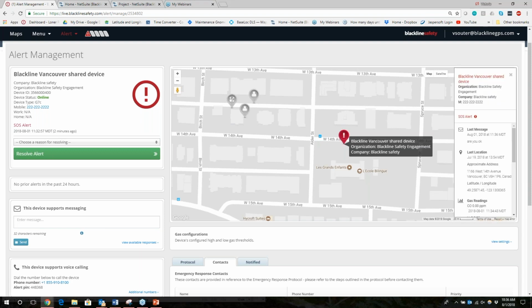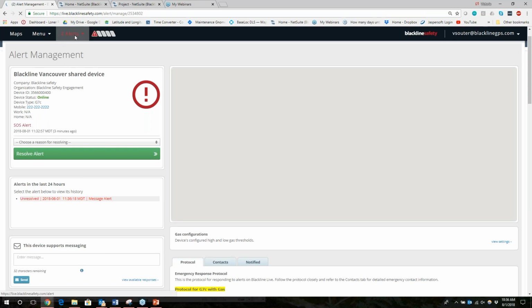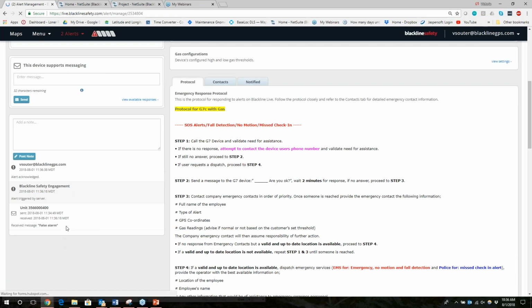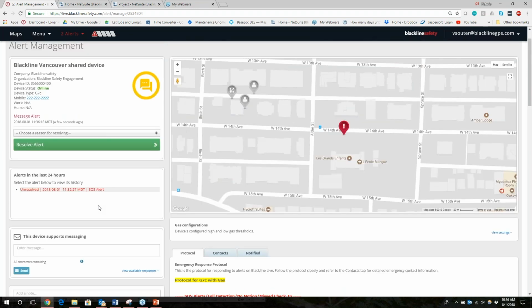Okay, and I'm just going to respond back so you can see. So I've just responded back to that text, which you will see come in shortly. So it's pretty quick here. And when I look at that message and acknowledge it, I can see that I wrote back false alarm. And then I can choose whether I resolve the alarm, write my notes, put some notes in the section, post a note, but then I want to resolve the alarm.